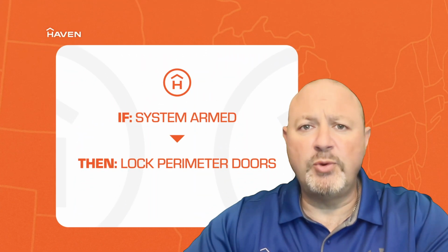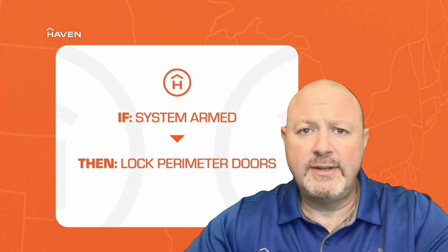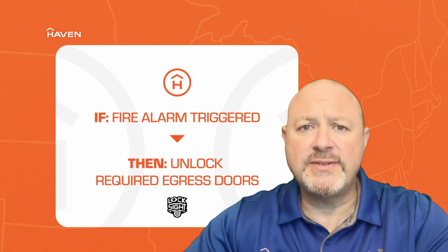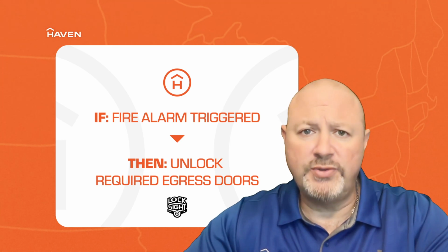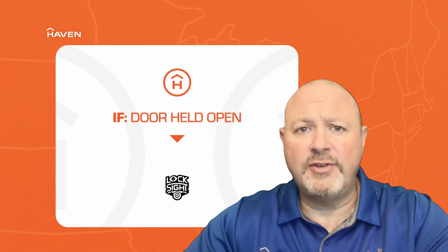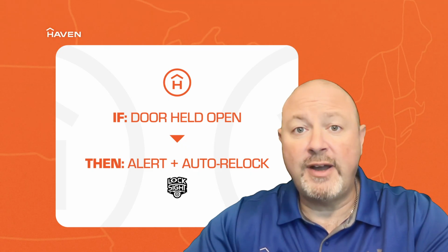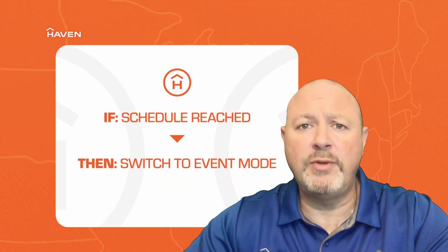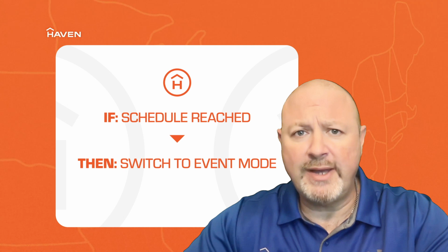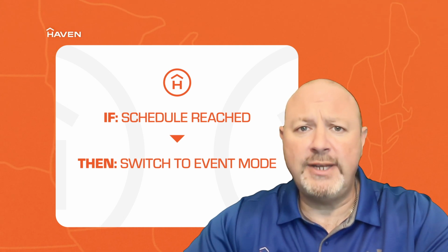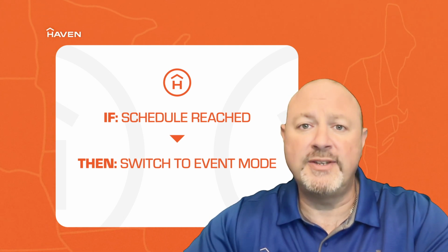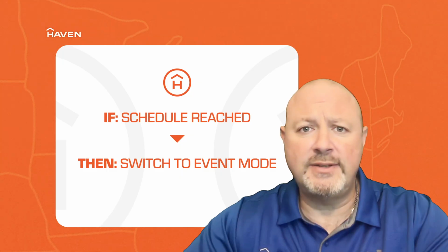Use Alarm.com rules to respond to arming state, time schedules, sensor events, and user roles. Bundle actions into scenes such as open, close, event mode, and after hours audit. LockSight overlays confirm door held timers, verify auto relock, and raise targeted health notifications. Tie everything back to compliance. Any required egress door must unlock on fire alarm as specified. Capture those settings door by door.